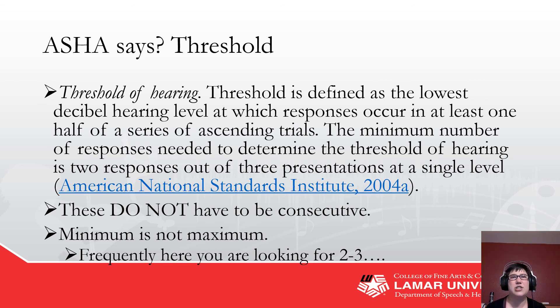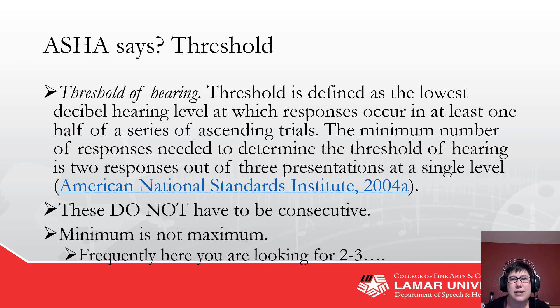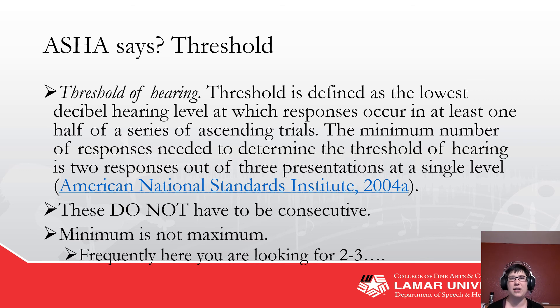How does ASHA define threshold? The threshold of hearing is defined as the lowest decibel hearing level at which responses occur in at least one half of the series of ascending trials. The minimum number of responses needed to determine threshold is two responses out of three presentations at a single level, pulled from the ANSI standards from 2004. They do not have to be consecutive — statistically it's likely they would not be.